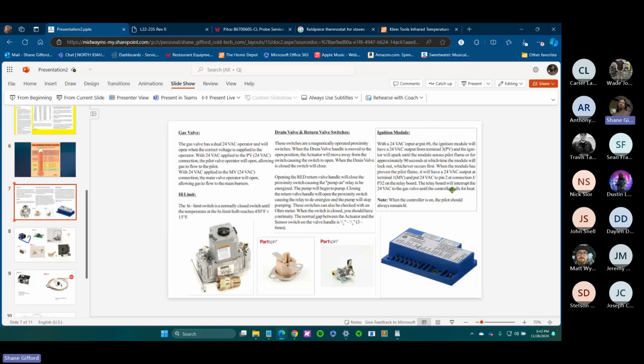So the major components of any cooking appliance, relating to oil fryers, you've got your gas valve. That looks like a resettable limit. Pilot assembly. These things right here are going to be your most common cause of failure, I believe, in most cooking appliances. This would be hooked up to your pilot valve on your gas valve, and as long as you've got proper flame rectification or volts DC, i.e. millivolts.